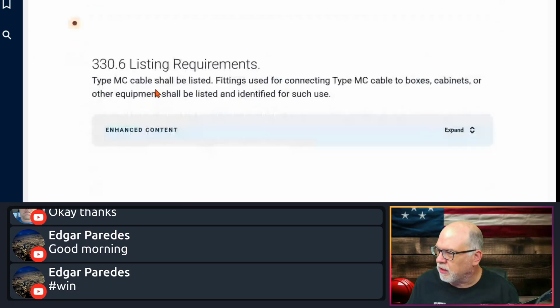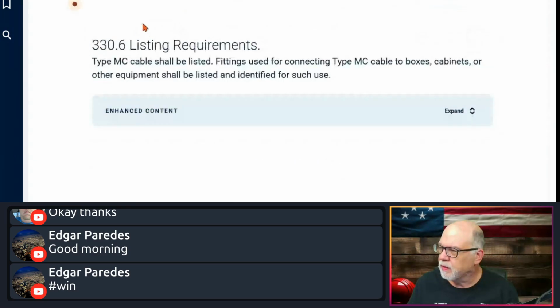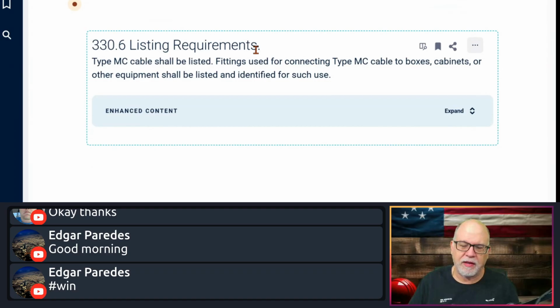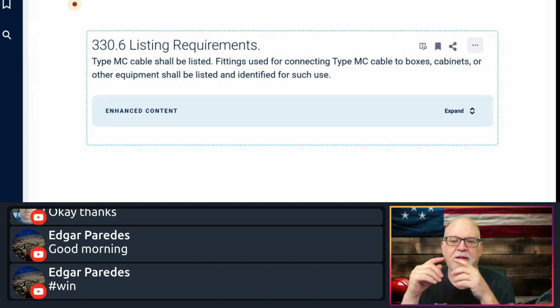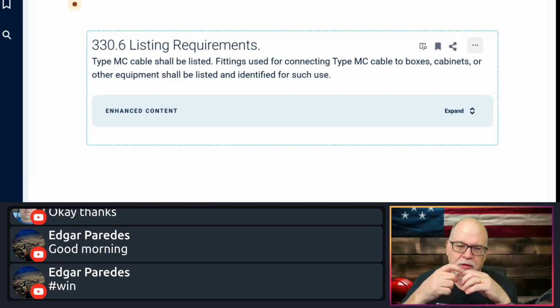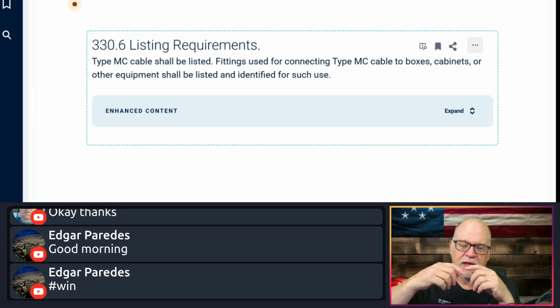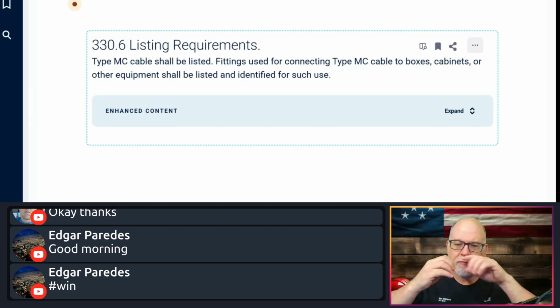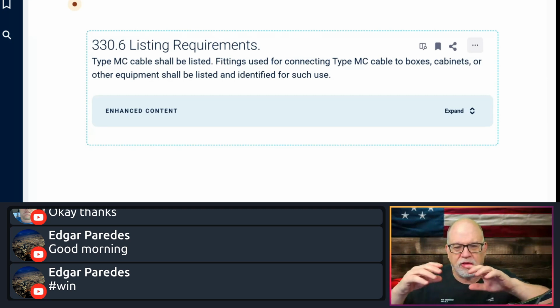And we're just talking MC today. Listing: all MC cable has to be listed, as a manufacturer of MC. Now, the listing for this is UL 1569, in case you folks didn't know. You've heard me talk about it enough. UL 1569 is the listing for metal-clad cable. Now, interestingly enough, y'all should know that metal-clad cable comes in many flavors. You've got the interlock, which is what we all typically use. Basically, it's a strip of metal that gets bent around, like a mandrel device that actually curls a beak, so that as it goes over, the conductors run through it. The metal comes off a big reel and wraps around, and it gets formed around the conductors as the conductors get pulled through this thing.